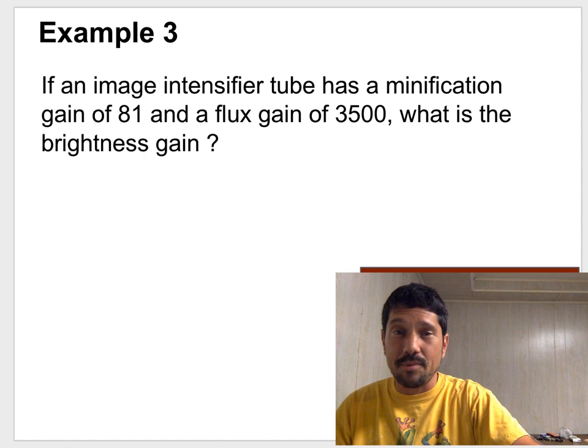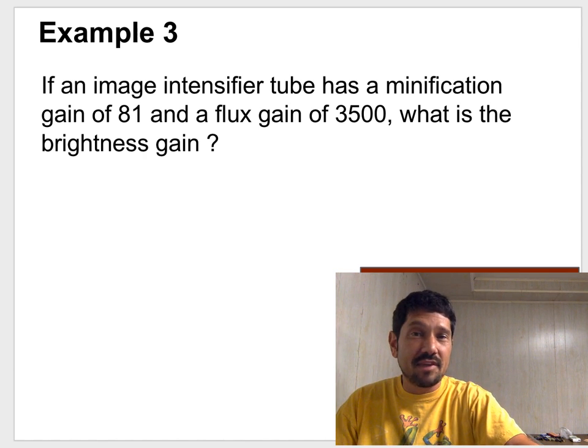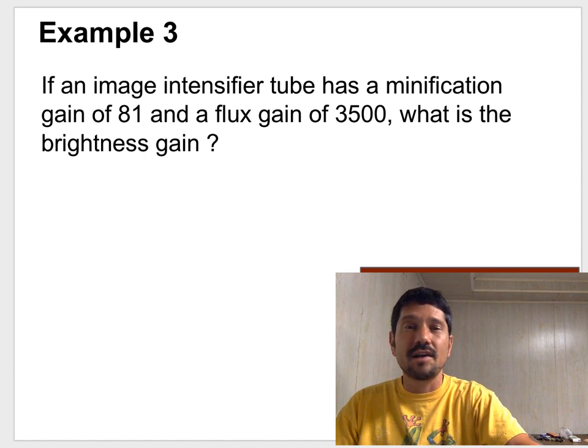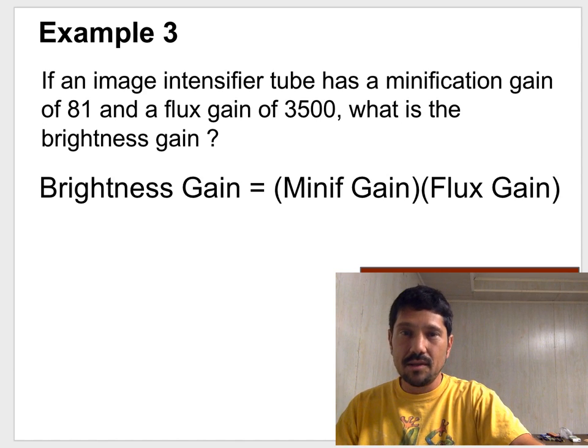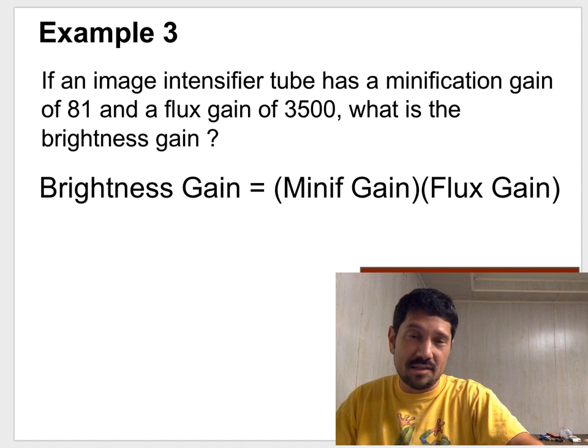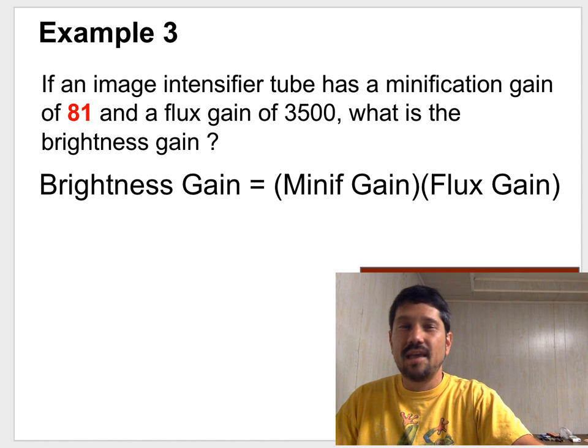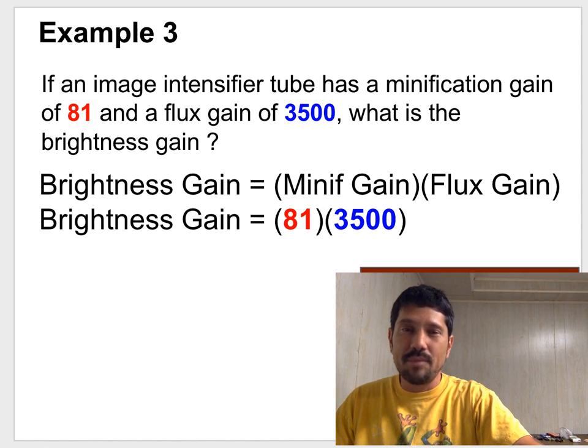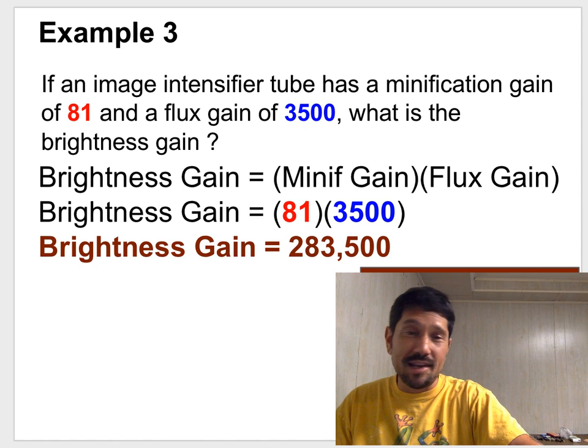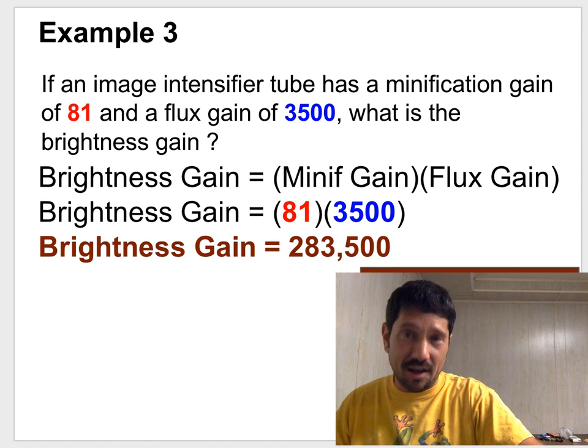So here's our last example. If an II has a minification gain of 81 and a flux gain of 3,500, what is the brightness gain? We would take our formula, and we would say 81 is minification, 3,500 is flux gain. We drop them in place and multiply them for an ugly number, 283,500.